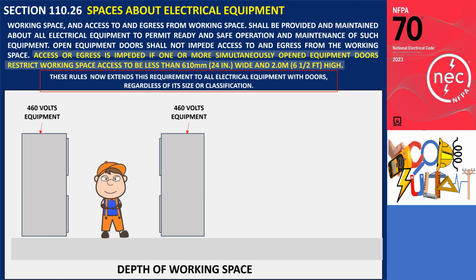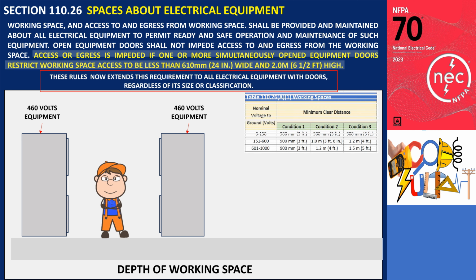To further illustrate this requirement, let's consider another example. We have two pieces of electrical equipment rated at 460 volts, and the installation falls under condition 3. Since the voltage is 460 volts, it falls within the range of 151 to 600 volts. According to Table 110.26(A)(1), the minimum required distance is 1.2 meters or 4 feet.